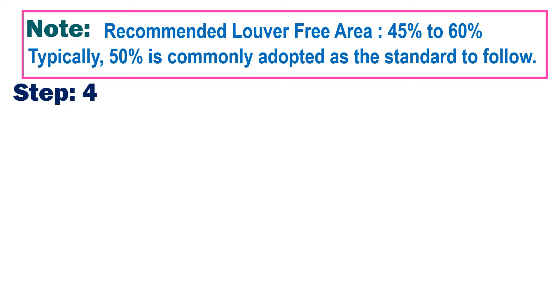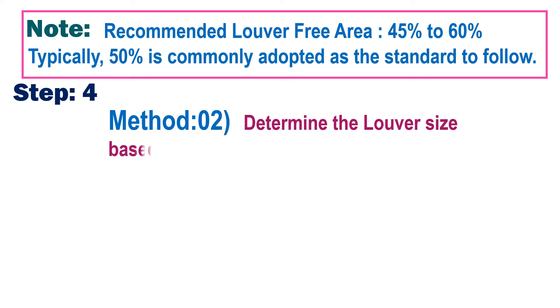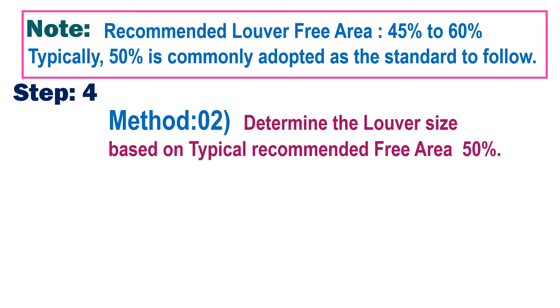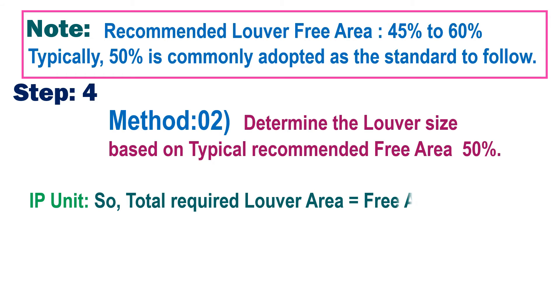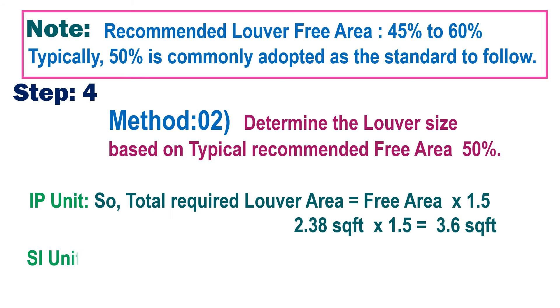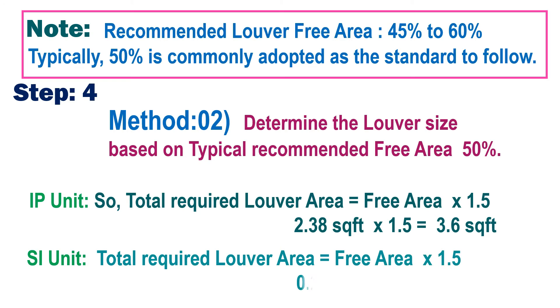Most cases use 50%. Step 4, second method: determine the louver size based on the typical recommended free area of 50%. For IP units: Total Required Louver Area = Free Area × 1.5, so 2.38 × 1.5 = 3.6 square feet. For SI units: Total Required Louver Area = 0.23 m² × 1.5 = 0.35 square meters.